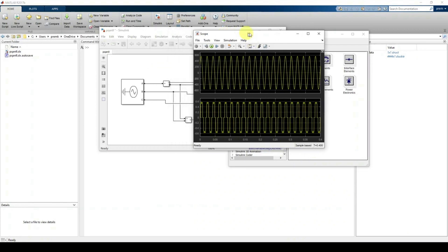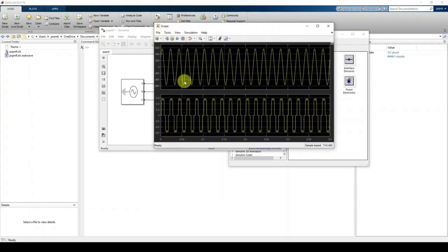The results are now visible. The top waveform is the source voltage and the bottom is the source current. You can see that the source current is non-sinusoidal — this is because of the nonlinear load connected to the source. Due to this load, the input current quality is affected and is non-sinusoidal, so the Total Harmonic Distortion of the AC source current is increased.